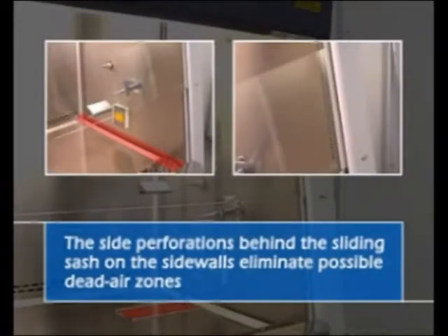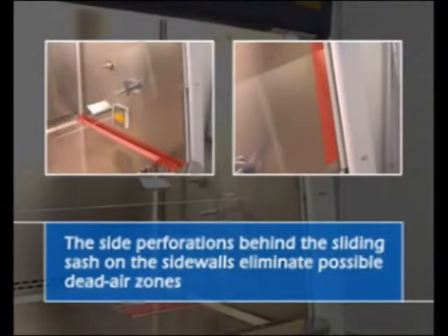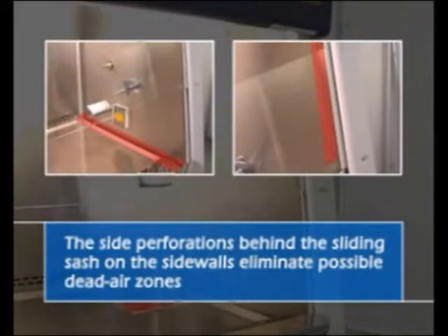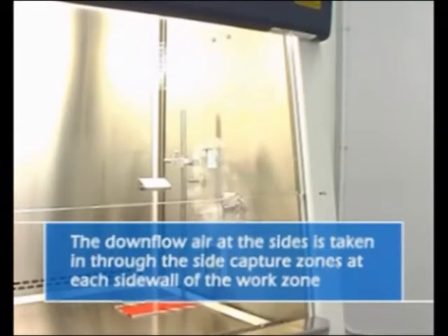For additional safety, the lab culture cabinet side walls are fitted with side perforations behind the sliding sash to remove possible turbulent air pockets from the work zone. A smoke generator placed near the sidewalls illustrates the airflow into the enhanced side capture zone and the sidewall perforations.